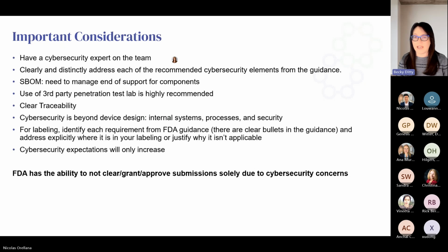We've already talked about the SBOM and the penetration testing and traceability. As I mentioned earlier, cybersecurity is beyond device design. As part of your cybersecurity processes, you also need to identify how you're keeping that software secure as you're developing it. What internal systems are you using? How are you managing permissions? How do you know you've downloaded the correct software onto the device during the manufacturing process? Or if a user's doing it themselves, how do they know? So it's beyond just device design.